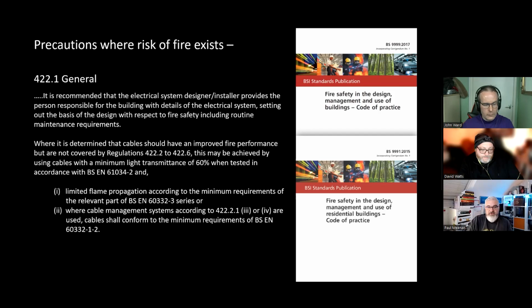Where it is determined that cables should have an improved fire performance but are not covered by regulations 422.2 to 422.6, this may be achieved by cables using a minimum light transmittance of 60% when tested in accordance with 61034-2 and are limited flame propagation to another series of standards, and where cable management to 422.3 and 4 are used. Cables should conform to the minimum requirements of 60. God, there's a lot of numbers in this, isn't there? Basically, in a nutshell, from what we've seen, I don't know what 60% transmittance is because I don't own that standard. Forgive me all. I don't own that standard. But what I have read is effectively fire rated cables and don't use plastic trunking.